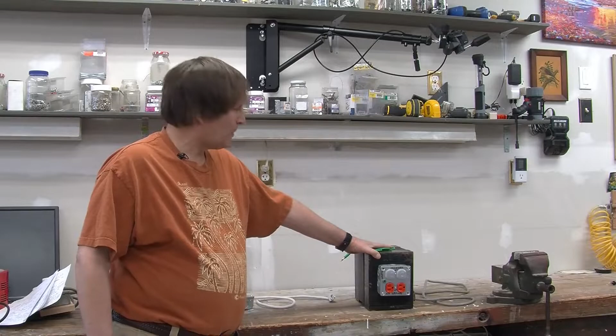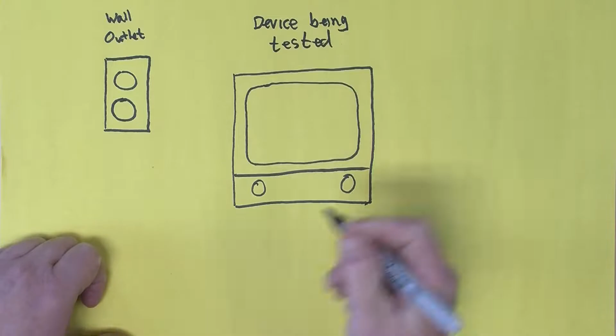The isolation transformer is probably the older of the two devices. It's been around since I was a kid, and its main purpose is to break the connection between the source of electrical power and ground. That's critically important, because when you zap yourself by accidentally touching something live, the typical return path of current is through you, then through the ground, and back into the neutral of the electrical system.